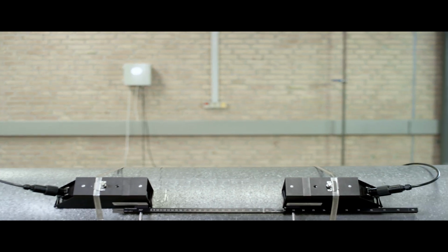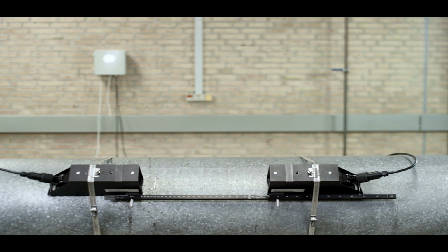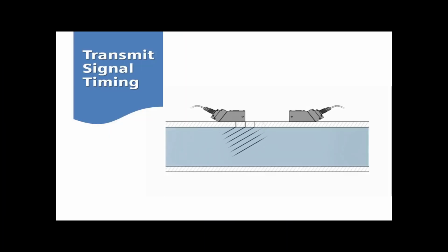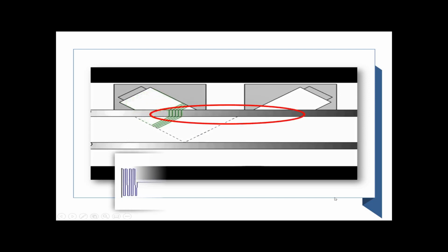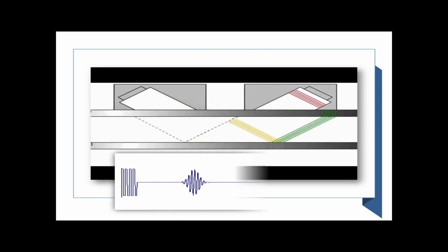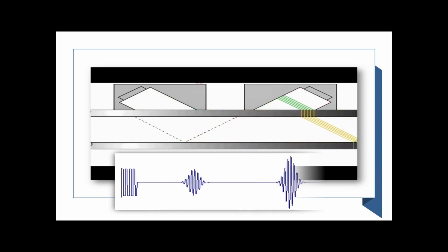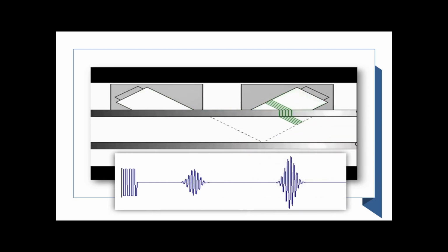First, the rules. In order to facilitate this test, your flow sensors must be installed in reflect mount and on a metallic pipe. When the sensors are in reflect mount, sonic energy is transferred into the pipe wall, which travels along the wall and is detected by the receiving sensor, as this animation illustrates. The fluid signal, the one that passes through the flow stream, arrives much later. This is the characteristic wide beam or Lamb wave signal we've pioneered.